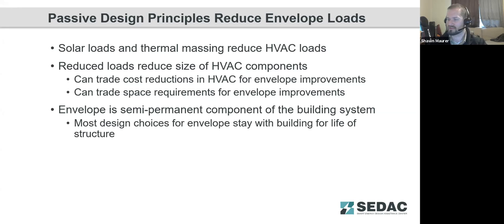Even for a typical office building, taking advantage of those loads can have a significant impact on the size of the HVAC equipment. If you can reduce the size of the HVAC equipment, you can trade costs for envelope improvements, and you also save space in the building. Because that HVAC system is smaller, the ductwork can be smaller, and the mechanical rooms that house that HVAC equipment can be smaller. If you're placing it on the roof, the loads on the roof can be smaller, which you can trade off structurally. So there are a lot of trade-offs where you can improve the envelope, which is a permanent component of the building, and that will take away from the expense you have to put into an oversized HVAC system to handle excessive solar loads or something like that.